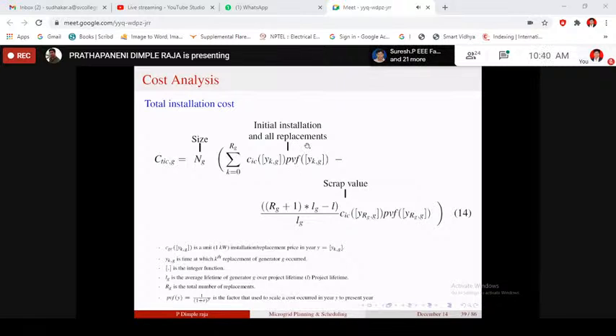That factor we have to consider using the present value function, and RG is the total number of replacements. So this covers the initial installation and all replacement costs. We also have to calculate the scrap value. For example, if the microgrid lifetime is 25 years but the generator lifetime is 28 years, it may exceed after replacements, so we have to consider the scrap value.